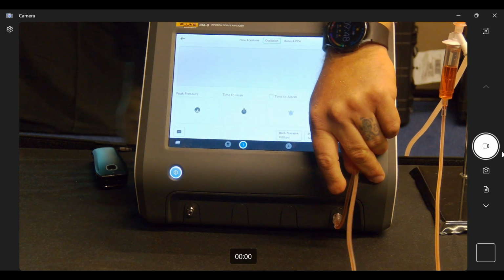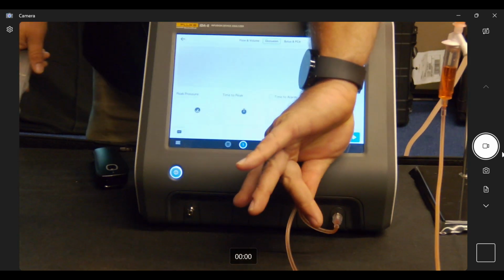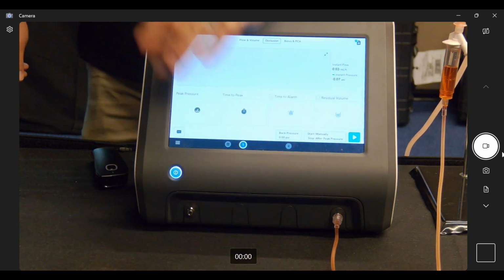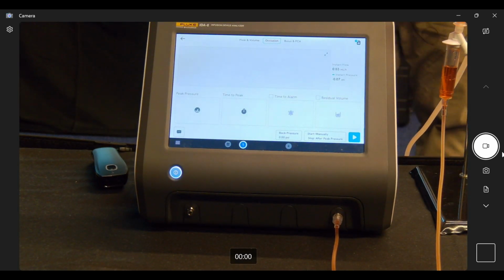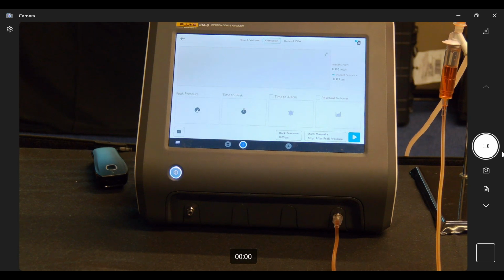So if you have this included and the pressure is released, wouldn't it be nice to know how much volume is built up in that line? So we can also measure that residual volume that's coming out. You didn't have to move stopcocks, you didn't have to move ball valves, you didn't have to slide up tubing, you didn't have to do any of that. Only thing you had to do to flip from occlusion to volume was tap a screen.